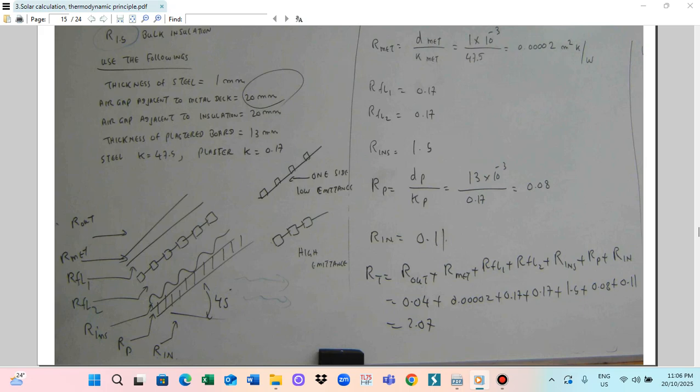In the program, calculate the U value for the pitched metal deck roof with a reflective white insulation and red ceiling with R 1.5 bar insulation. So because of the R 1.5 bar insulation, you don't need to calculate the insulation. You can utilize the 1.5. And then you also have to calculate the R plywood. R plywood is RP, which is dp divided by kp.